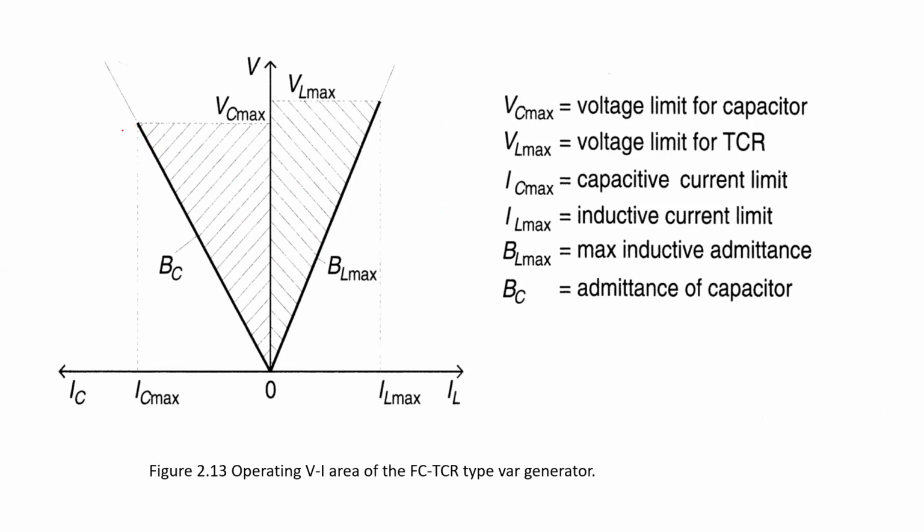Since the capacitor is a fixed capacitor, we found that in the previous condition there is no control area. But in conjunction with the thyristor controlled reactor, the effective value of the entire fixed capacitor and thyristor controlled reactor combination, the VAR, can be controlled.